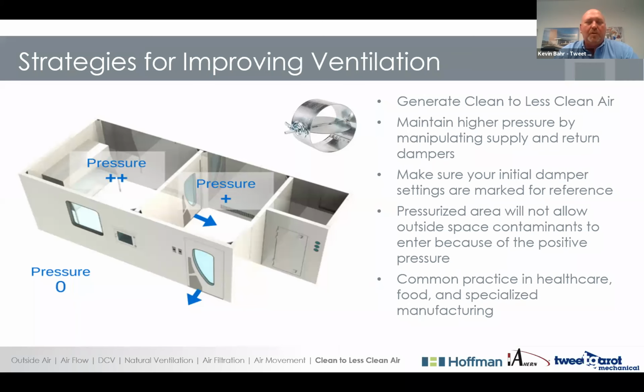Again, I'd recommend somebody from your staff or an air balancing person to document where they were prior, because that should adhere to what your initial design was. And after the fact, also document where you set them. The purpose is to keep a higher pressure in a space to not allow air from the surrounding spaces, that may be contaminated, to enter the higher pressure space. I'll give an analogy because it's the easiest way for me to explain it.